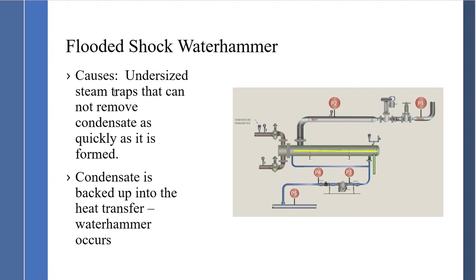Flooded shock water hammer is caused by undersized steam traps. As covered in segment one, sizing a steam trap requires understanding P3 and P4 — the differential pressure across the orifice. A key factor is understanding what P4 is based on the dynamics of the condensate header, P5. If the steam trap is undersized, condensate backs up into the heat transfer equipment. Heat exchangers are not designed for condensate or flooded conditions, and waves occurring inside due to the heat exchanger configuration will produce water hammer.